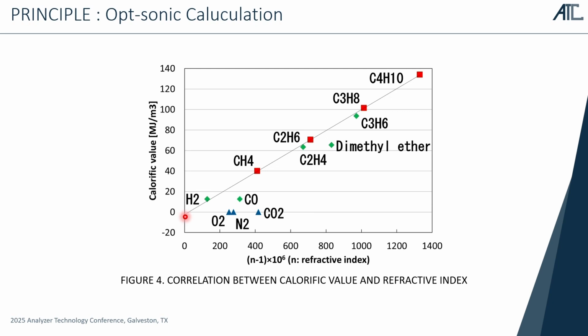And then the straight line from here to here shows the sensitivity curve. And as you can see, methane, ethane, propane, butane, these are on the sensitivity curve. But as you can see, like the blue gases here, for example, CO2 doesn't have a BTU, but the CO2 has a refractive index. So once pure CO2 is measured, our optical sensor measures it as pure methane, and it shows like a 40 megajoule, 1,000 BTU on the display. So that was a kind of characteristic, and that was a kind of issue we faced before.